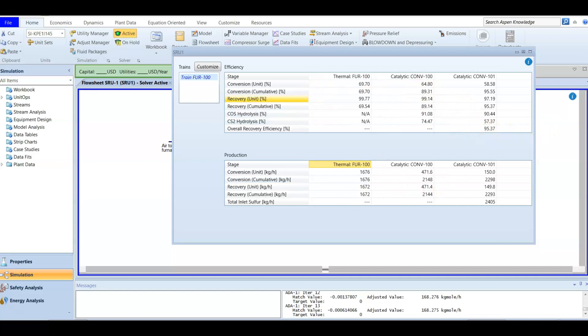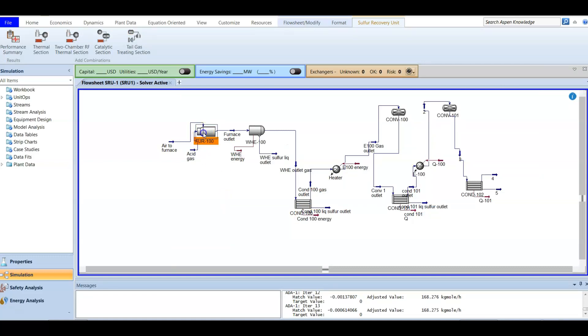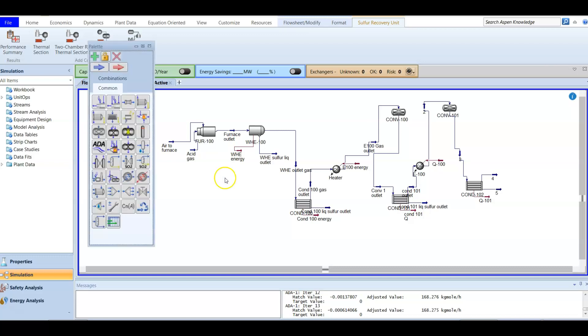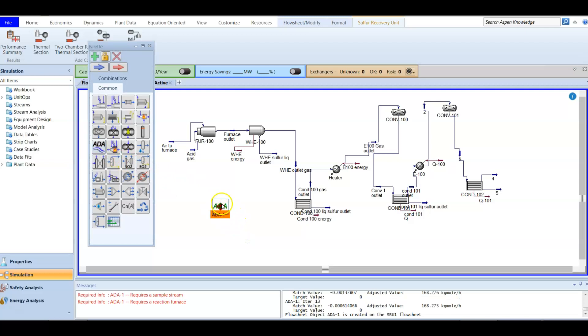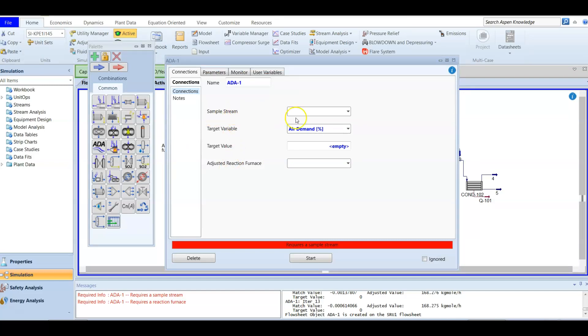These units are doing well, but we can improve performance by improving the furnace. As mentioned before, the oxygen amount should be controlled because it affects the total conversion percent. In this case, we are going to add an ADA — an Air Demand Analyzer — to control and optimize the flow of air, which burns H2S and converts it to SO2.